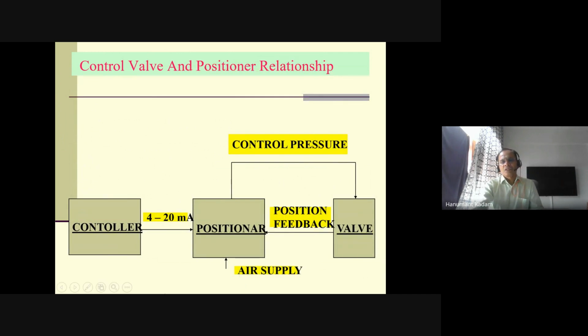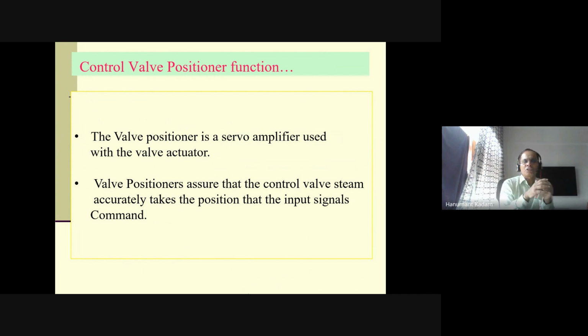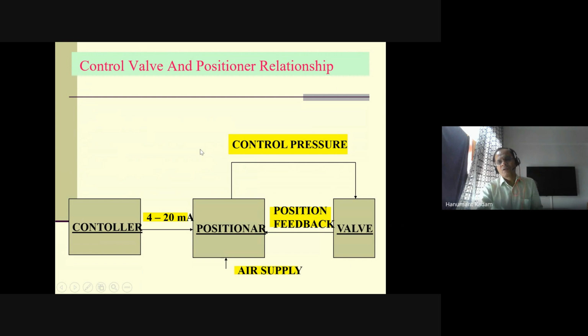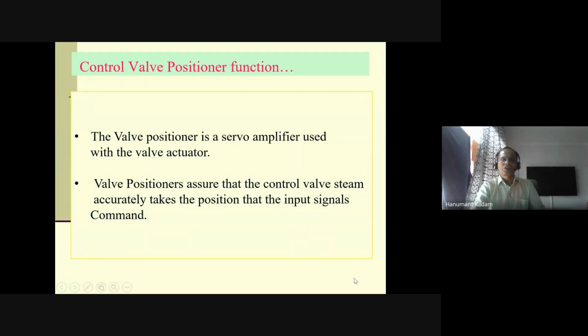So if you see the relationship, the positioner needs three inputs. One, air supply; second, the controller signal; and the actual position of the valve, that is the position feedback. Then you will get a control pressure output here. So if you see the function, the valve positioner is a servo amplifier used with the valve actuator. It acts like a servo amplifier. It's amplifying. The valve positioner assures that the control valve stem accurately takes the position that the input signal commands. So whatever control pressure signal comes, suppose it is 3 to 15, maybe 12 psi, or maybe 9 psi, the valve has to always maintain that position. So that is a very important function of the control valve.